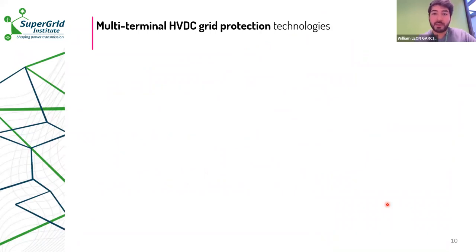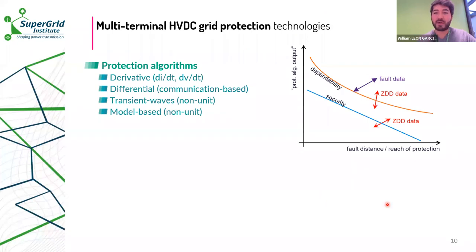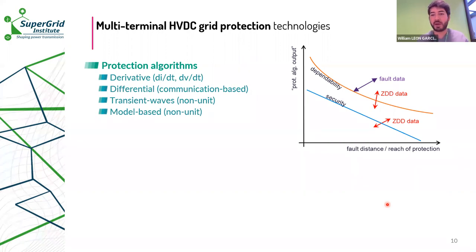Regarding MTDC protection technology, algorithms implement the protection strategies. Known algorithms today include derivative-based algorithms using rate of change of current or voltage, communication-based algorithms, transient wave analysis, and model-based analysis. The choice of algorithm depends on fault distance, fault resistance, and other system characteristics. Each algorithm is evaluated in terms of dependability — the capability to detect faults inside the protection zone — and security — the ability to ignore faults outside the zone.